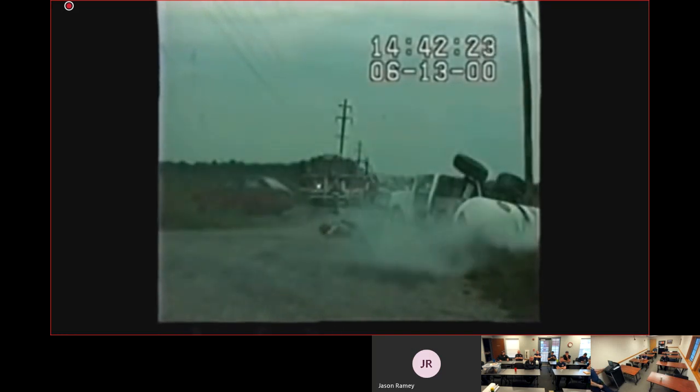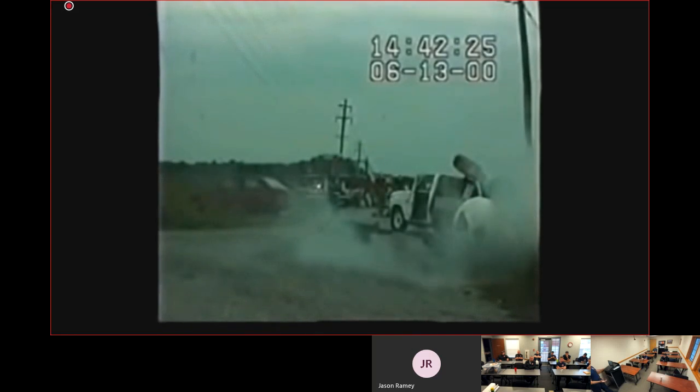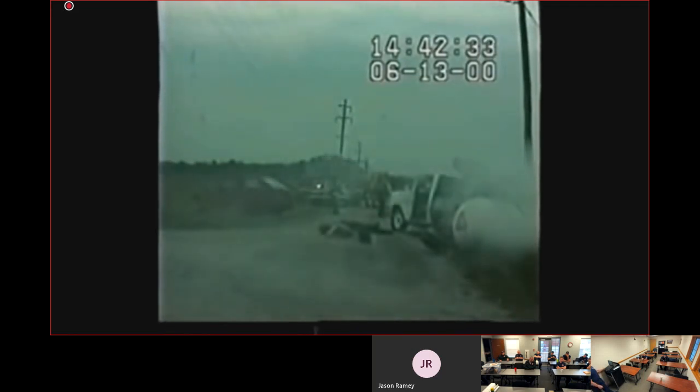You'll see here, they come up, they'll deploy the hose line to start hitting, and as soon as you do that, if you put a wide fog on this cloud, the respiratory issue and the vapor issue goes away. There is still a chemical release. There's still anhydrous ammonia in the area, but the risk to you immediately is greatly reduced once we get that water on it, and we dictate where it goes instead of letting it sort of find its way.